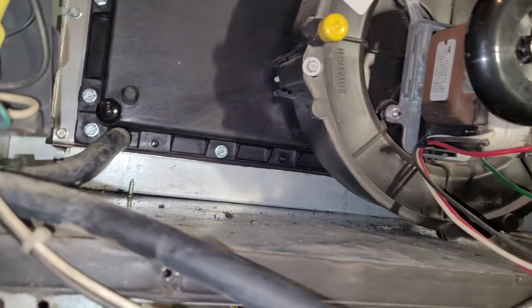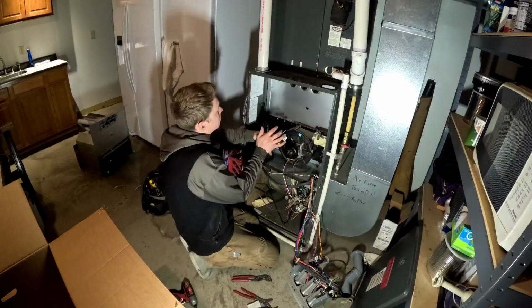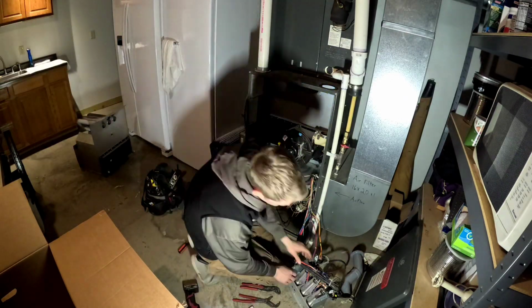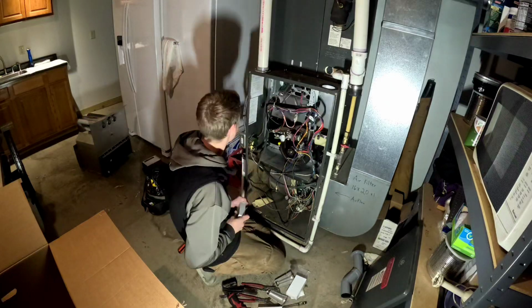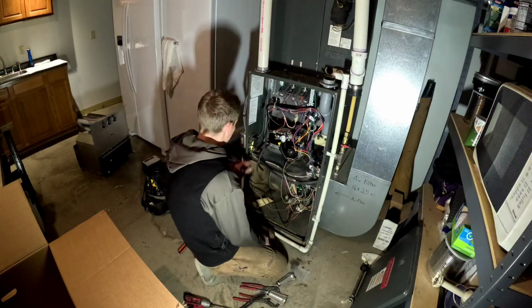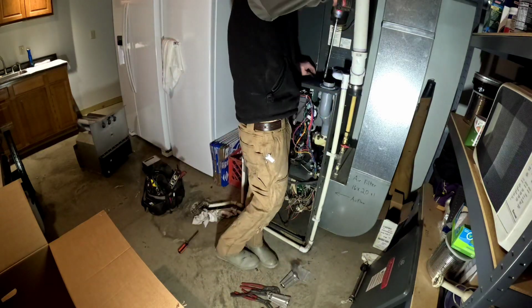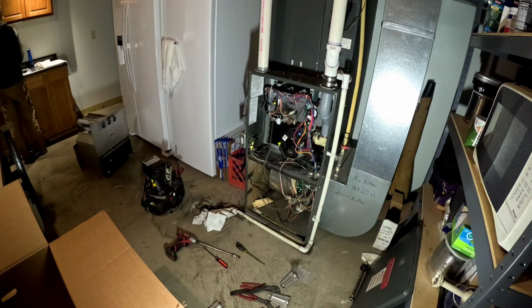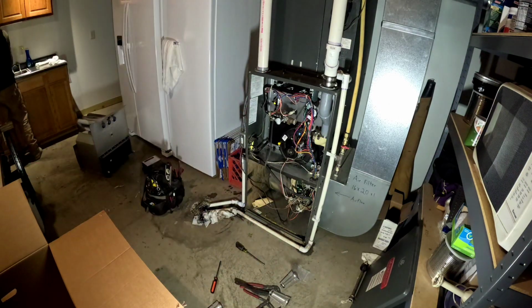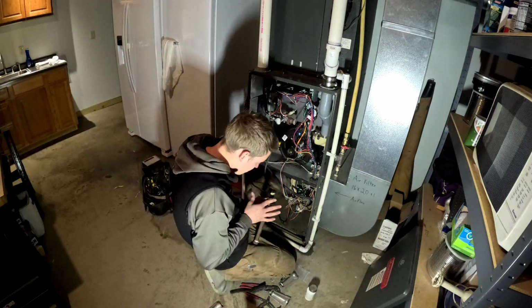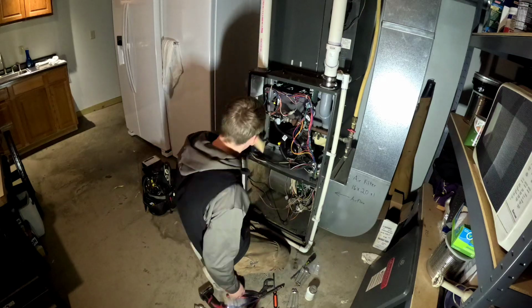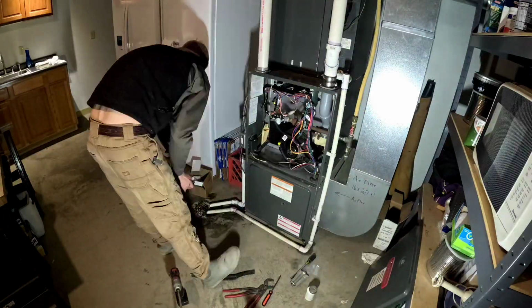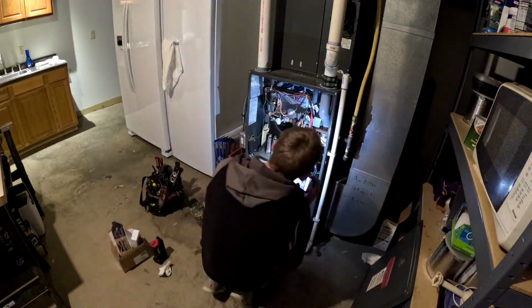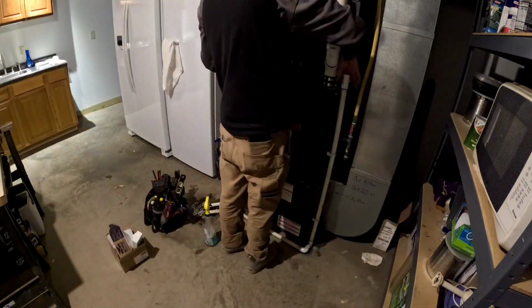There were a few components, like some of these hoses that go through and the condensate trap, that I actually took off of the furnace and washed before the final assembly. You don't want to put plugged up stuff back onto the furnace, so just make sure if there is something that needs to be cleaned, you do it before you put the furnace all the way back together. In this case especially, there was a lot of black sludge built up in the condensate trap and in the tubing. I like these Goodmans in that the condensate trap is just mounted on the outside of the furnace and is very easy to clean out. Pulled apart and cleaned the trap, put everything back together.